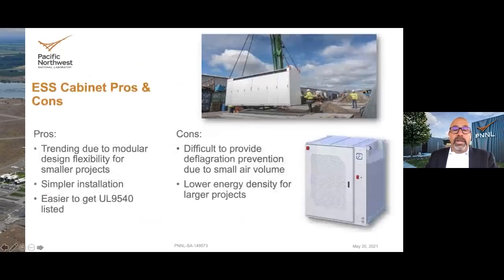The industry is moving towards more modular designs because these can be listed to UL 9540, and for large systems they just multiply them. But some of the cons are that there's a lot less free air space inside, so if you do have a thermal runaway, you need to manage those gases.